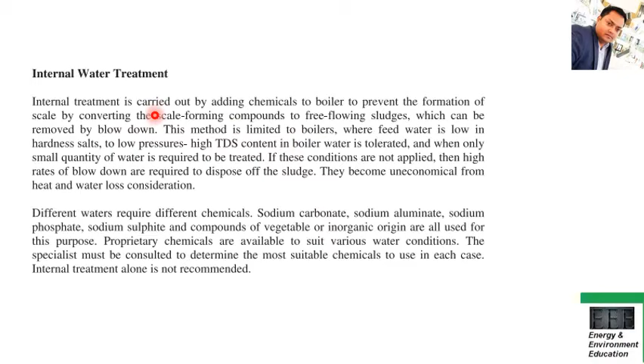As you can see from the name itself, the internal water treatment was done inside the boiler using chemicals, which are used to separate the sludges or deposits inside the boiler, or to prevent corrosion inside the boiler, friends. And external water treatment means you are treating the water externally, not inside the boiler. Externally, you are using different processes like the ion exchange process, the demineralization process, reverse osmosis, and the de-aeration process.